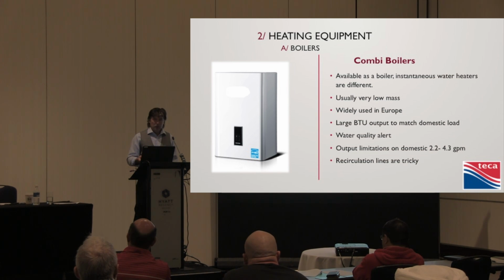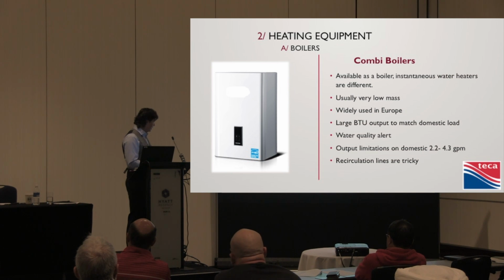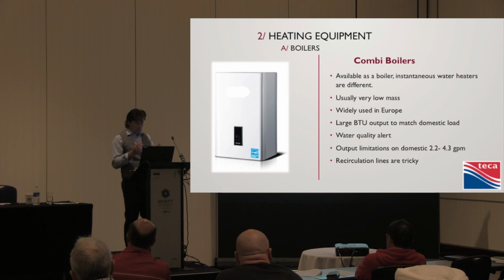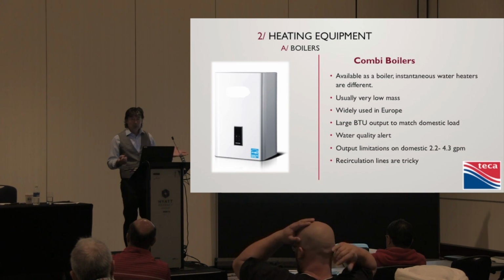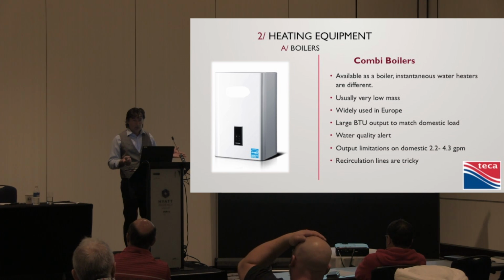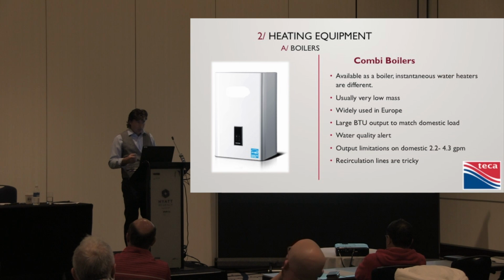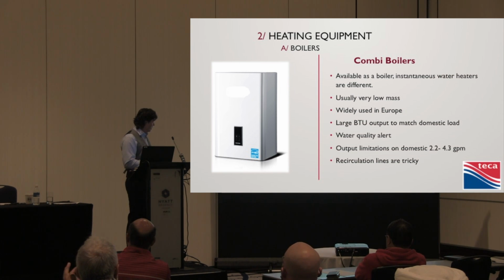I'm thinking that's in the drawback category because we just bought an instantaneous heater so we didn't have to have a tank. So it's acting as a bit of a buffer tank there. So there are these little add-ons that you've got to think about. Do you need a recirculation? Is your house big enough that you need a recirculation system? Think about all these things when you're deciding whether or not you want to use instantaneous water heating.